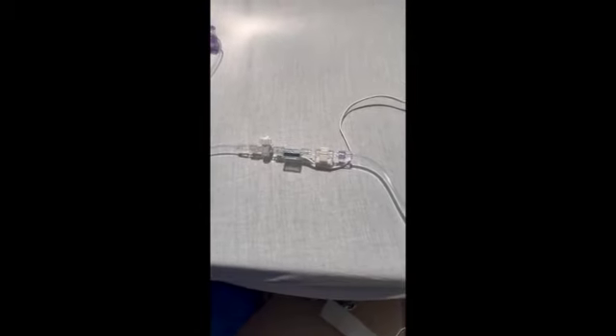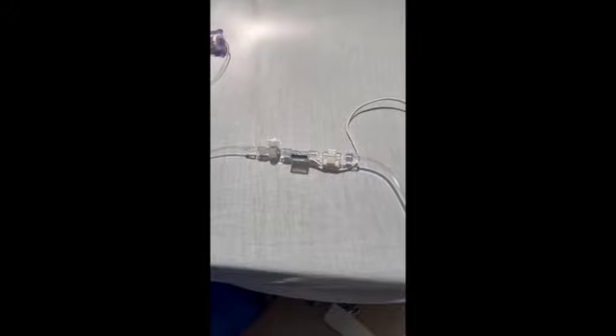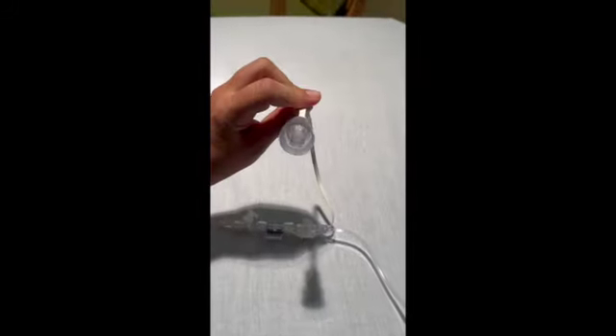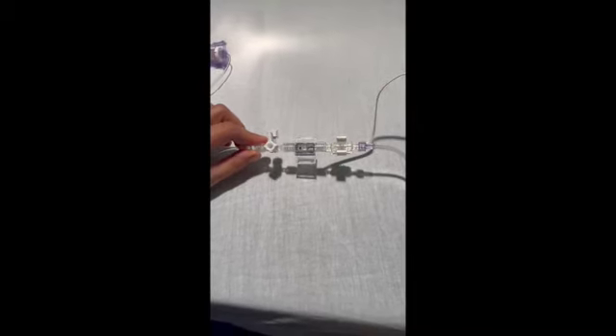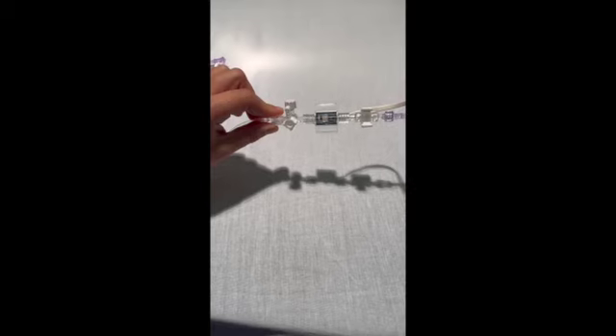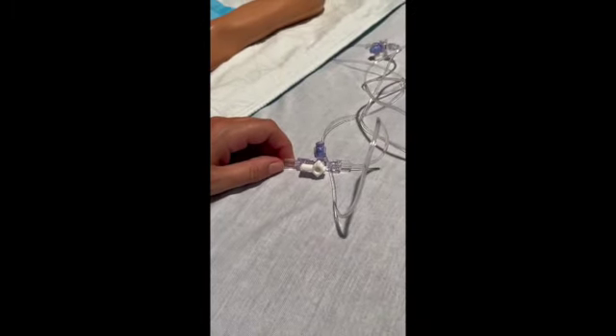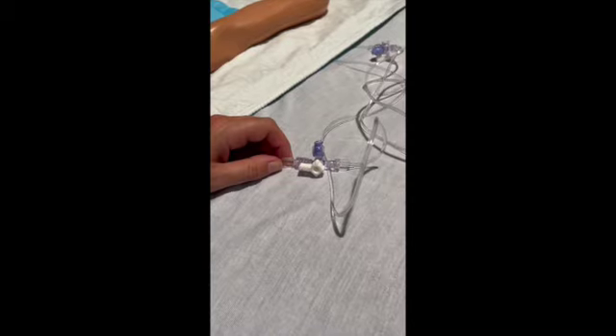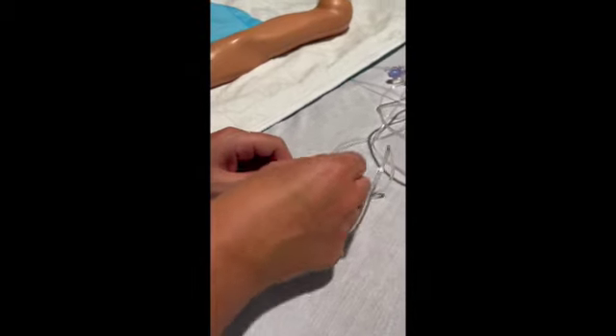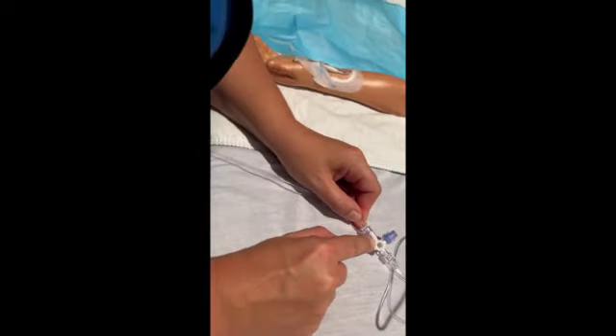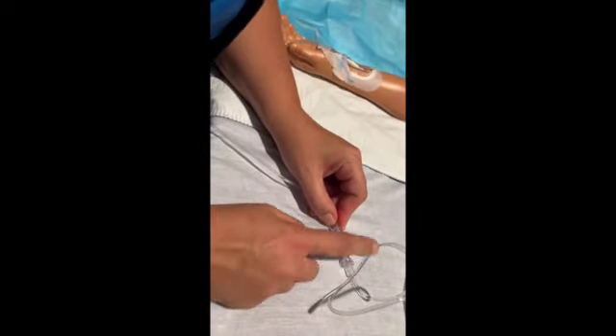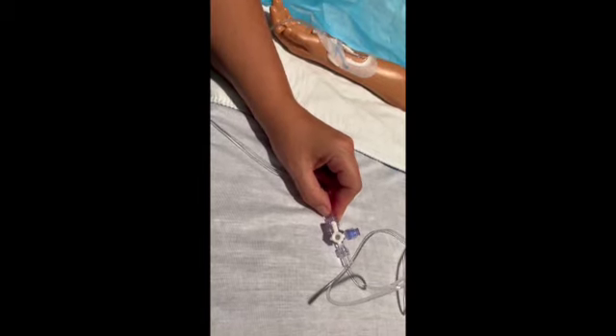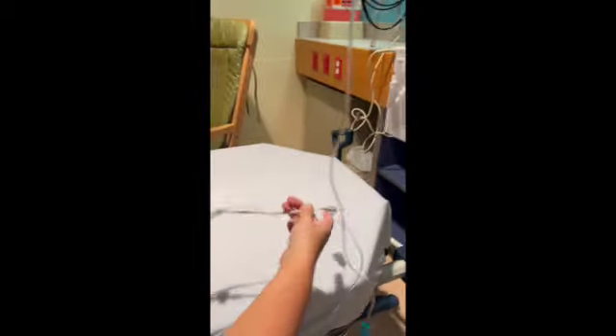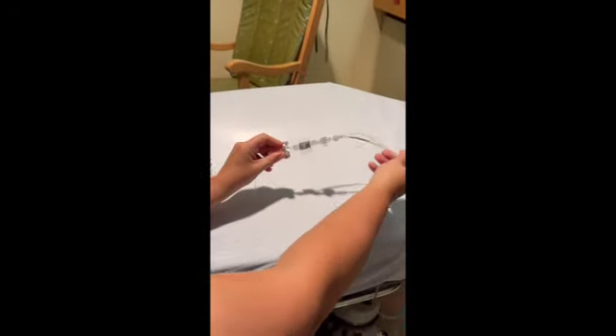With the Safe Set system, as well as the old system, you're still going to have the same connecting piece that attaches to your monitor. Nothing will change. We also need to remember the position of the transducer needs to be at the level of the heart at the mid-axillary line. One thing we also need to mention in terms of zeroing the arterial line when the patient arrives to the PACU: with the old system, you would remove the cap after turning the stopcock to the patient. You're still going to turn the stopcock to the patient, but you're not going to remove the cap because they're not removable. We had talked about this transducer needing to be at the level of the heart, mid-axillary line.